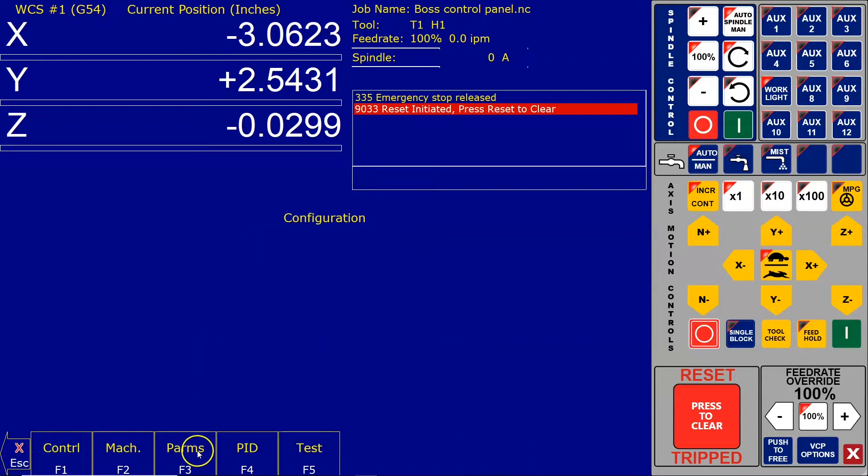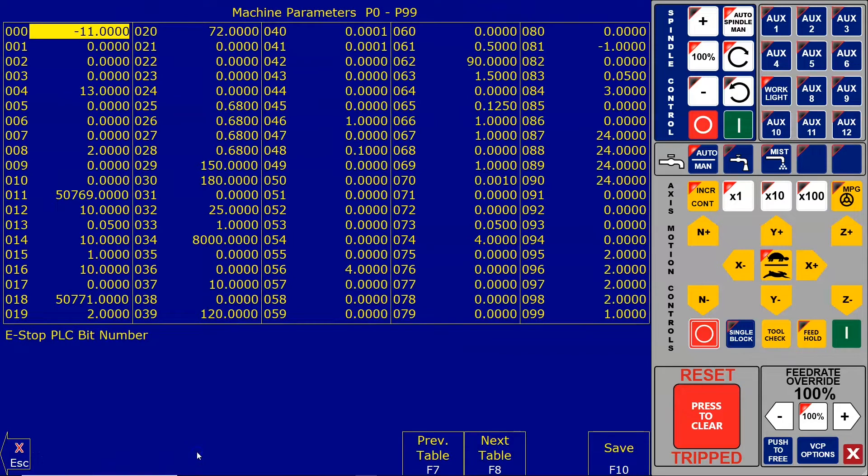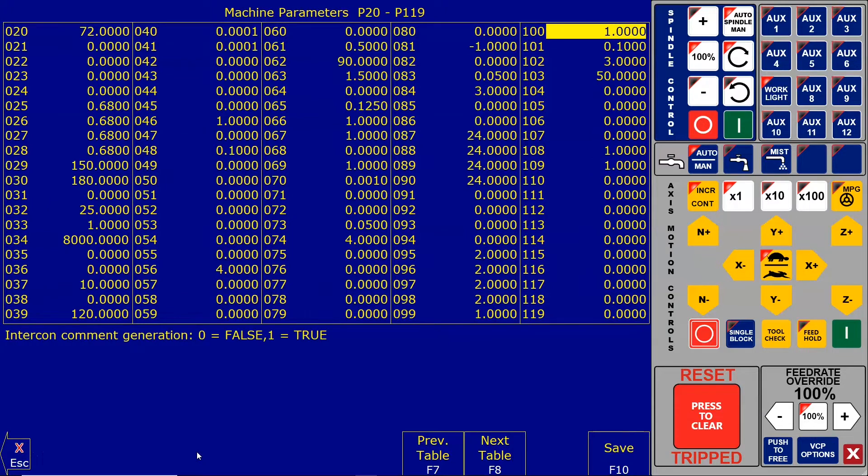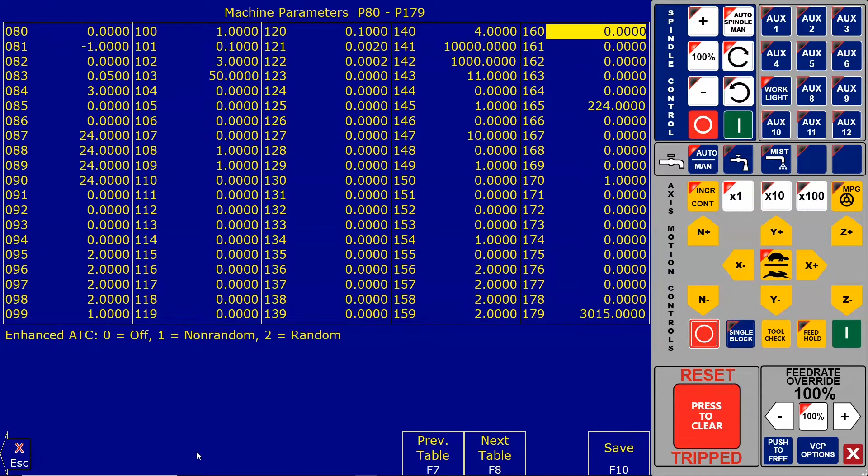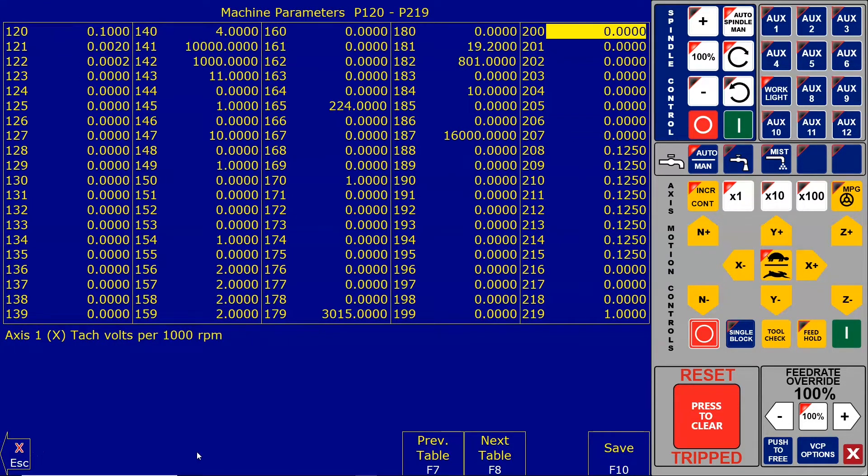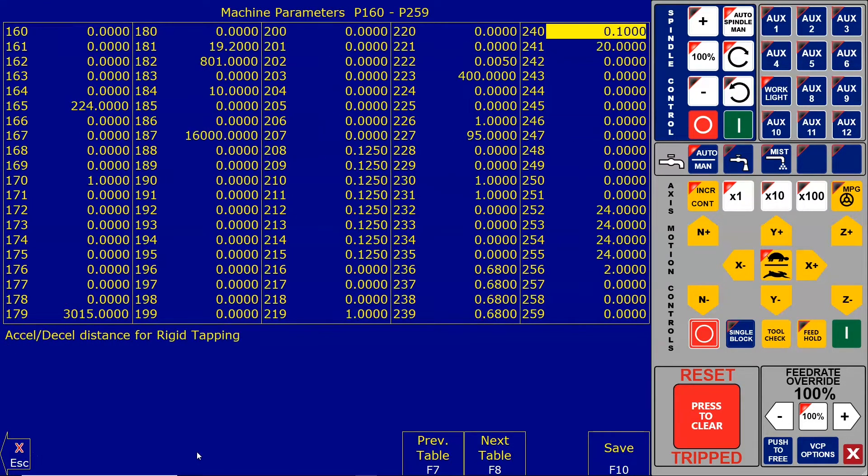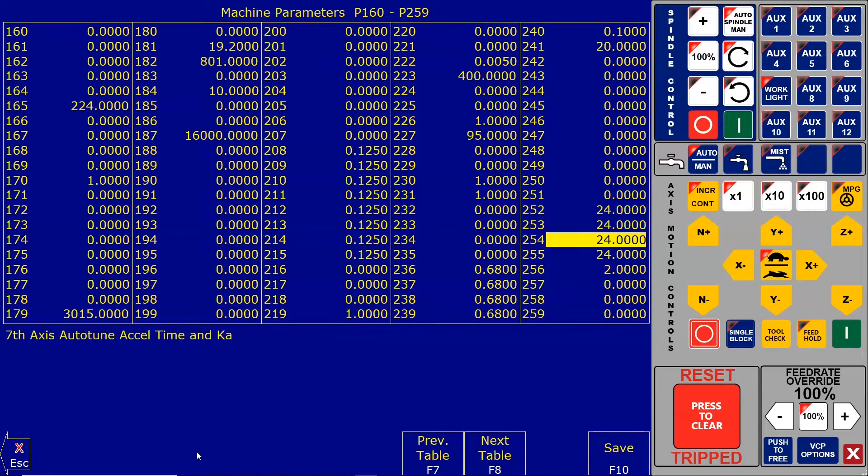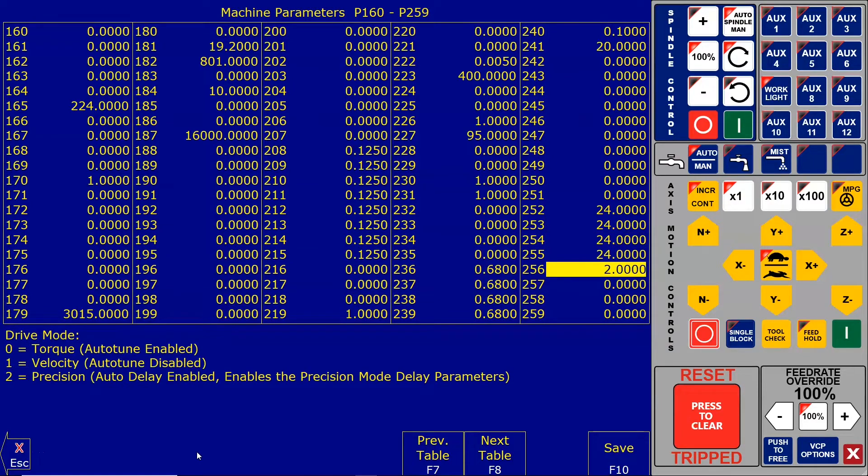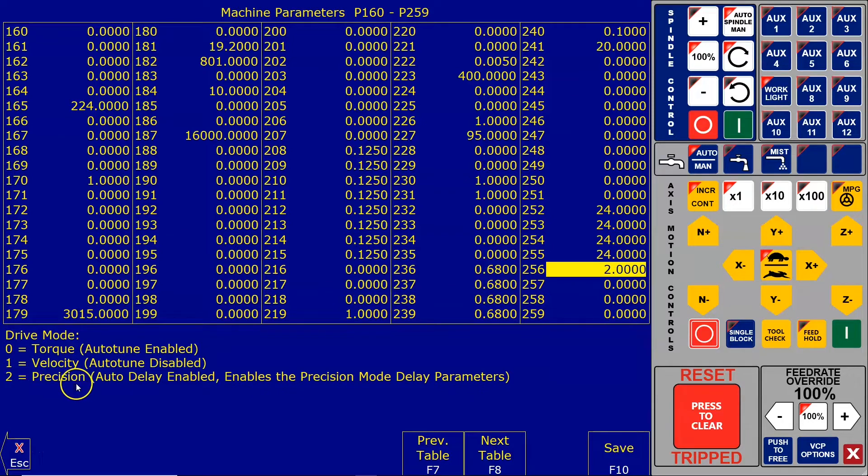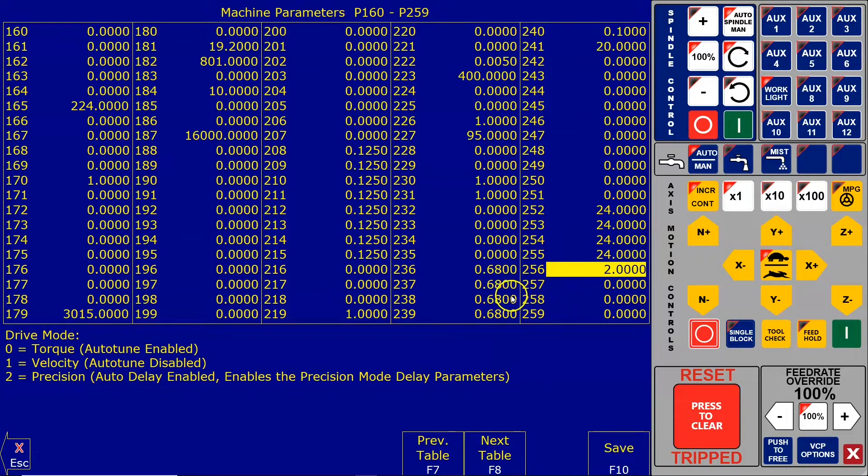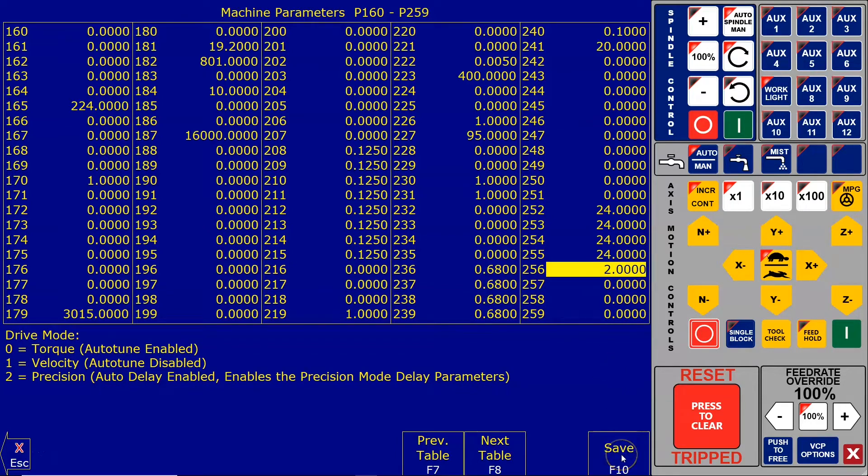I'm going to go into Setup, Config 137, enter. We're going to click on parameters and go to parameter 256, which is right here, and we're going to change that to two. There's a legend that says precision mode auto delay enabled. I've already changed that to two. When you've changed it to two, go down here and click save.